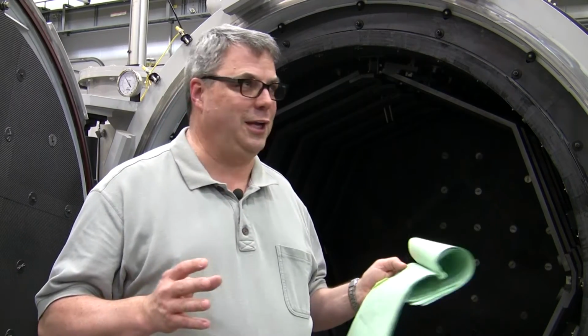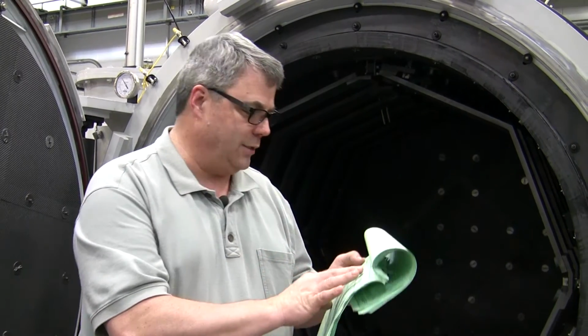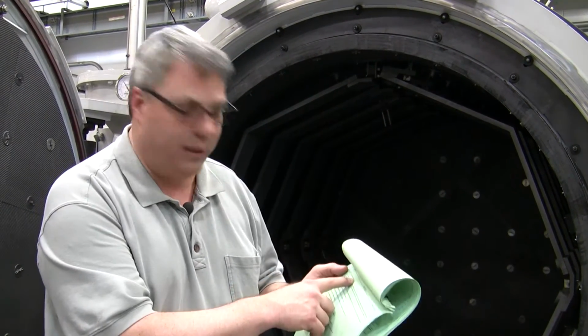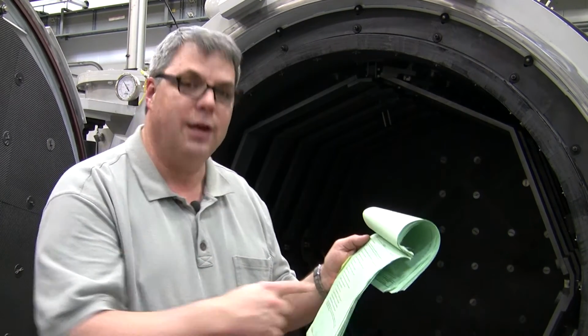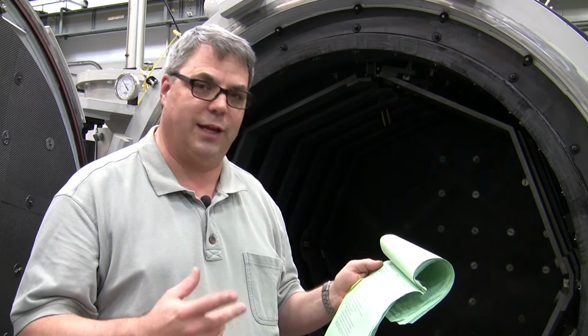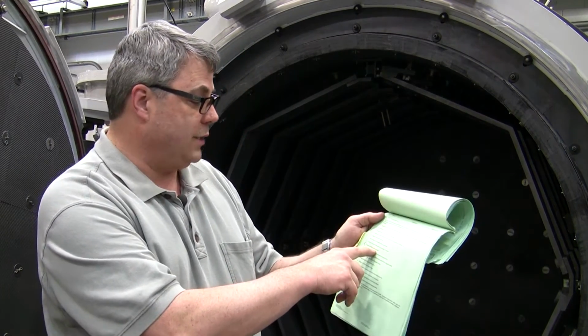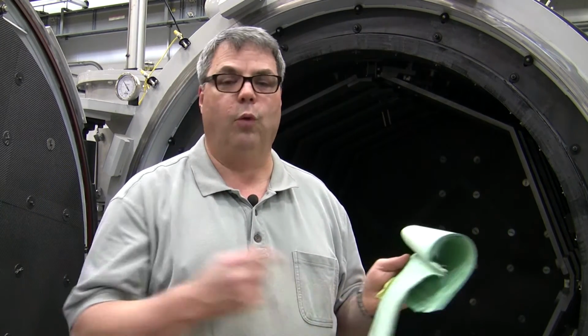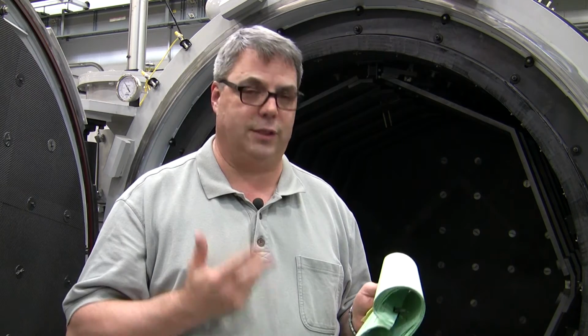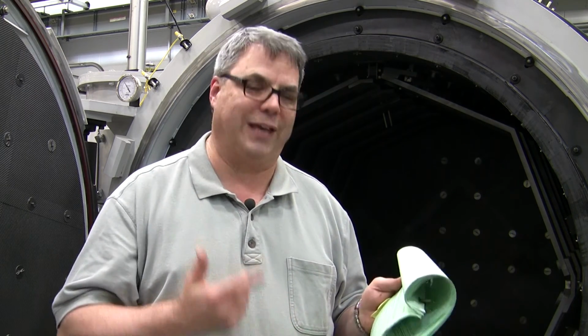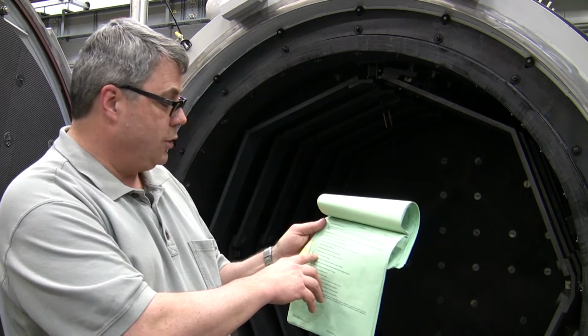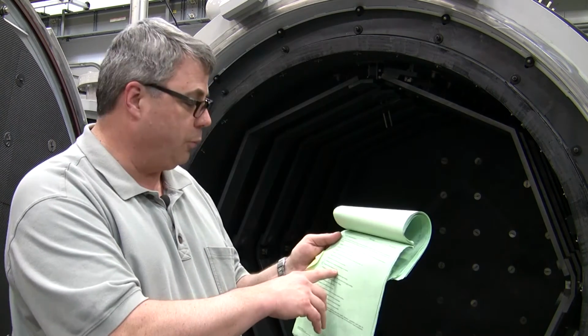Not trying to start any controversy or naysaying, but when you read things and it says 3.53 furnace modifications, and they give some examples of furnace modifications that may require recertification of the TUS and SAT. One is a change of control sensor location. So again, if you cannot prove where the thermocouple was prior to it being broken, and you put a new thermocouple in, even if they're from the same roll of wire with the same exact certification, you're changing the placement because you cannot prove where the thermocouple was prior to the incident. So as long as you're recording on your SATs or TUSs where it was and where it is when you're done with the survey, then you meet number H, change of sensor location, because you're not changing it and you can prove you didn't change it.